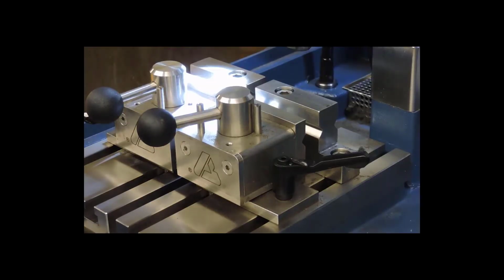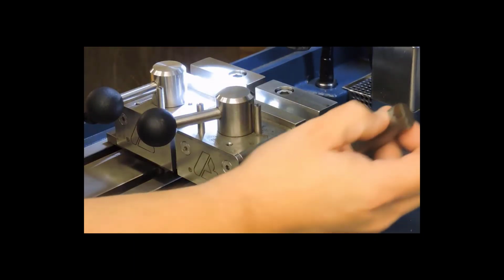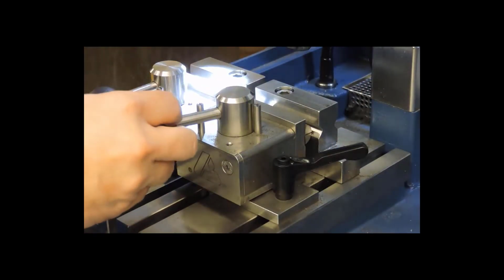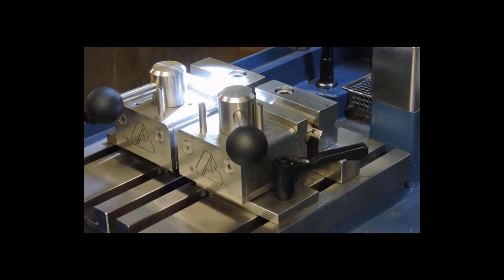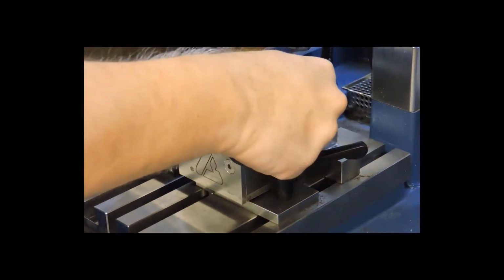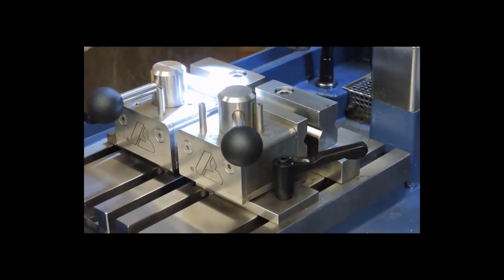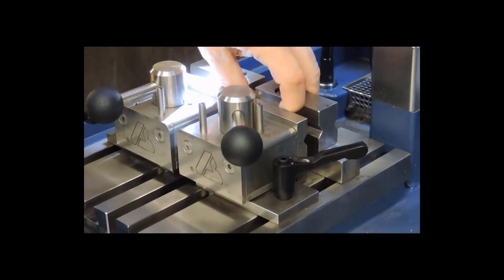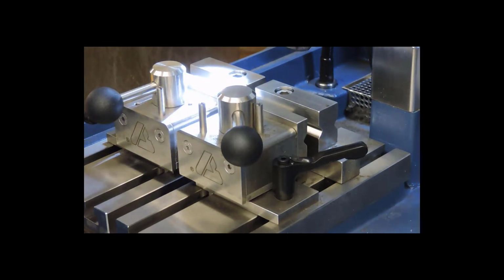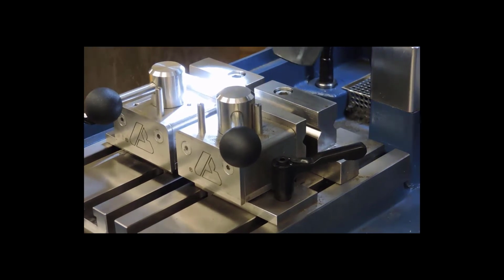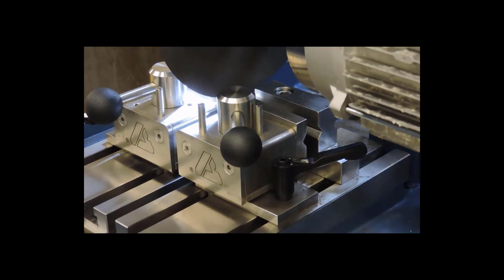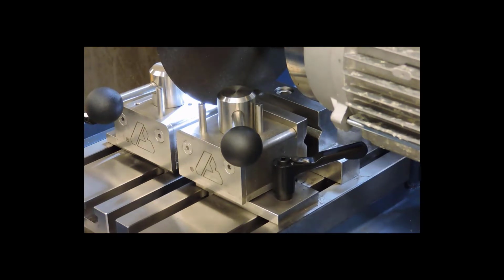So we've zoomed in on the vise. I place the bar, making sure that I don't cut the end with our identifying slots into this triangular slot. I bring the lever forward until I feel the slightest bit of resistance, and that will allow me to move the bar over to the left here and position it close to where I want the cut to be. Then I will reach around and bring down the cutting blade until it's almost touching the specimen, and now I can position the specimen for the cut.